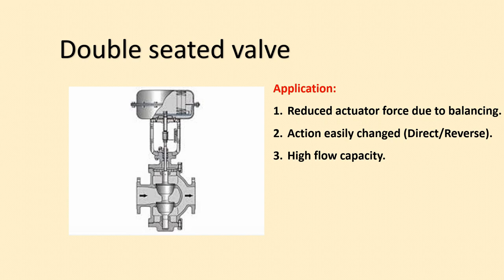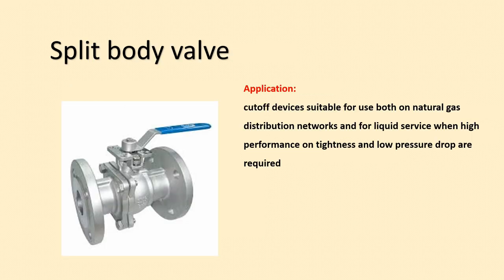Next is the double seated valve body, which has a two plug and seat arrangement. The main application of the double seated valve body is that it is used in high pressure piping because it reduces actuator force due to the balancing effect of the double seated arrangement. Another benefit is that it allows easy changeover from direct to reverse action, and it can handle high flow capacity — meaning a high volume of process fluid and gas — which is why the double seated valve body is used in those applications.